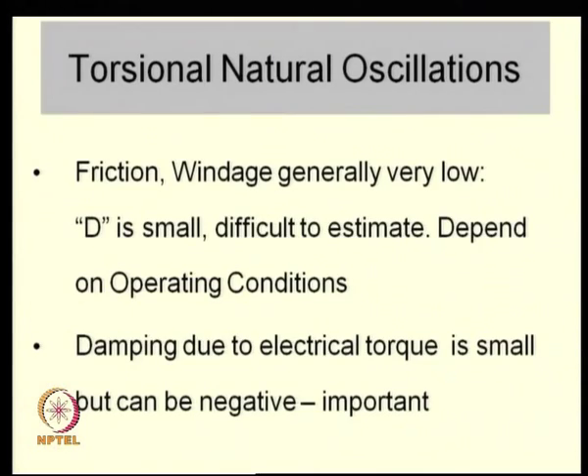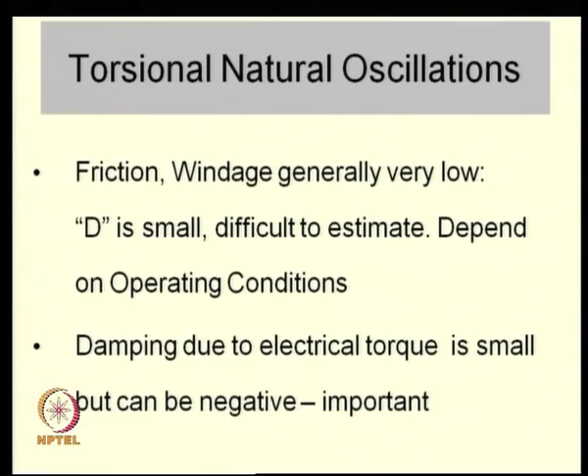Torsional natural oscillations — the natural oscillations of the shaft, turbine, and generator system — are effectively like a spring-mass oscillation, but importantly the friction and windage is very low. The damping associated with these torsional oscillations is actually quite small. Electrical torque also affects the torsional oscillations; one can look at it as an input. The damping due to electrical torque can be even negative, which means that the oscillations can grow.